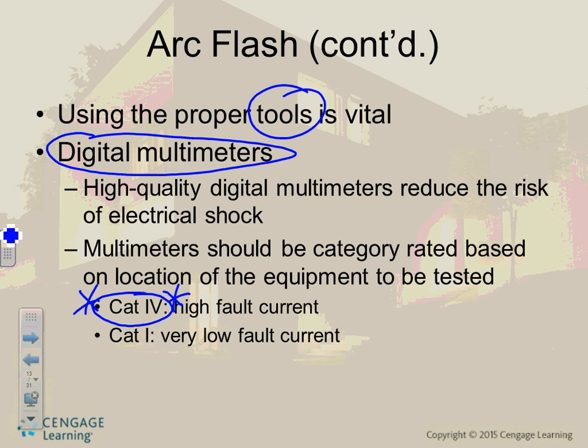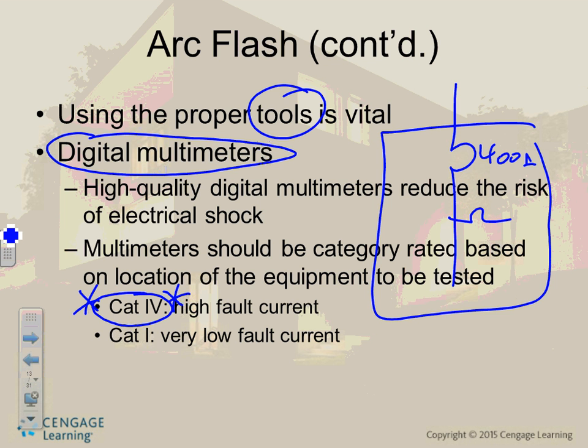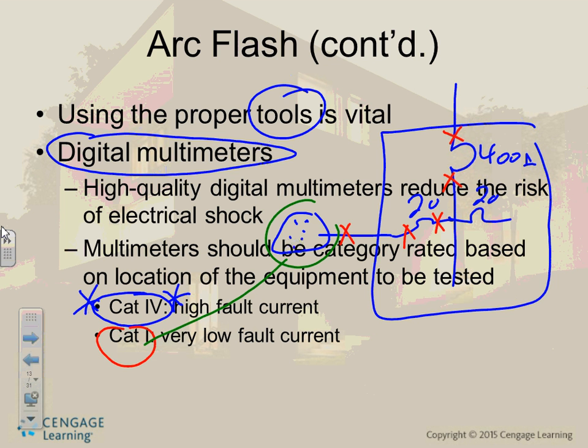So always, when you look at your meter, look for this rating. This one is the best, category 4. Category 4 means you can use it on a 120 circuit, a 480 circuit, inside a panel, on the line side or the load side of a disconnect. So if you have a panel like this, here's your 400 amp, and here's your 20 amp circuit coming out, like a circuit breaker or a receptacle. This meter can be used here, here, here, or here. A lower category meter can only be used in one specific place. Category 1, then 2, 3, 4 — category 2 can be used on this side, category 3 up to here, and category 4 covers everything. Always look for category 4 when you use your meters.